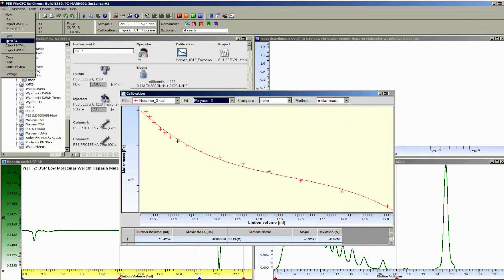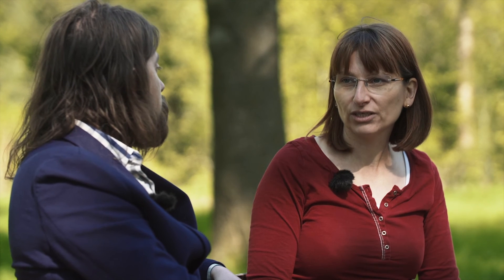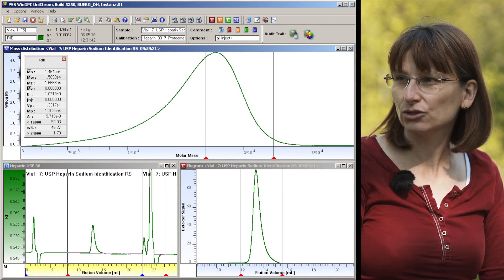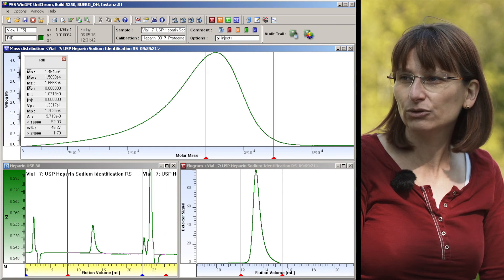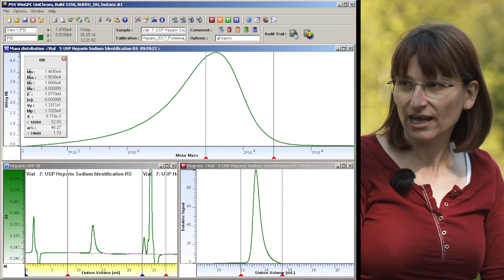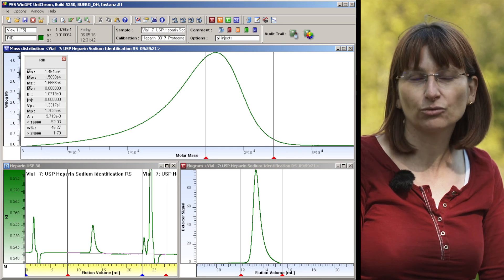What is quite important to realize is that you really need software that provides a true molecular weight distribution. Many HPLC softwares calculate molecular weight averages but do not convert a chromatogram into a molar mass distribution — they just replace elution volume with molecular weight and that's it. But this approach does not work when you need to measure the special parameters required for heparin analysis.